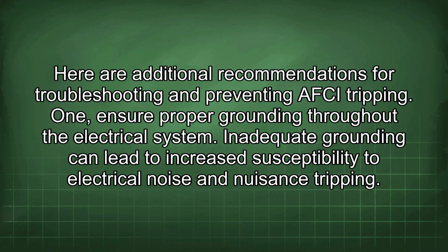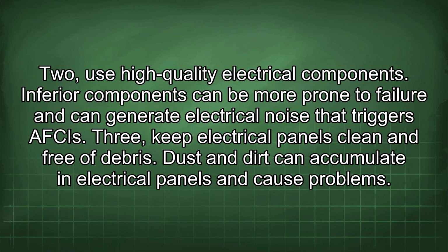Here are additional recommendations for troubleshooting and preventing AFCI tripping. 1. Ensure proper grounding throughout the electrical system. Inadequate grounding can lead to increased susceptibility to electrical noise and nuisance tripping. 2. Use high-quality electrical components. Inferior components can be more prone to failure and can generate electrical noise that triggers AFCIs. 3. Keep electrical panels clean and free of debris. Dust and dirt can accumulate in electrical panels and cause problems.